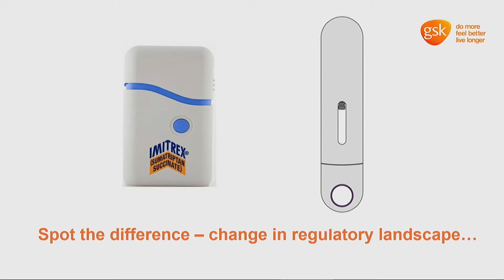I wasn't personally around when the first one was developed, but it was developed by a very similar team, using a lot of the same device development techniques that we use now. Some of them have been mentioned earlier, following these waterfall diagrams, making sure we got robust devices, all the verification testing that we need to do, but also human factors testing, something we've always done, and I think it's very important to do.